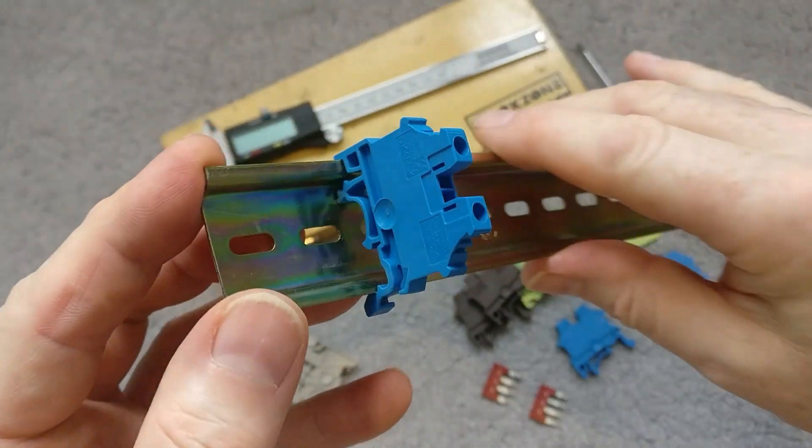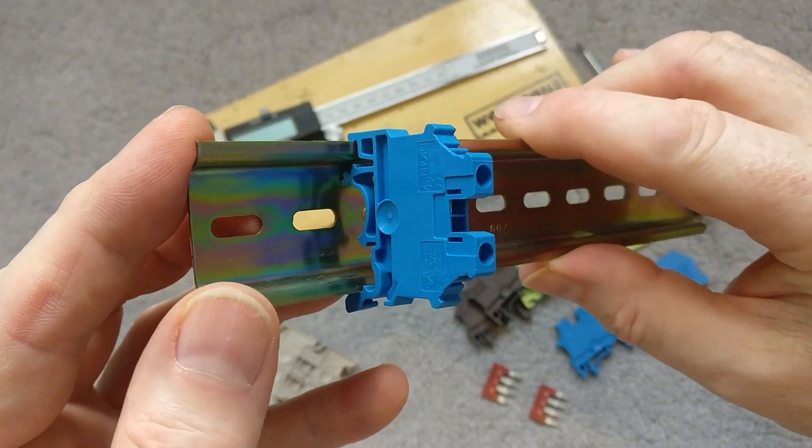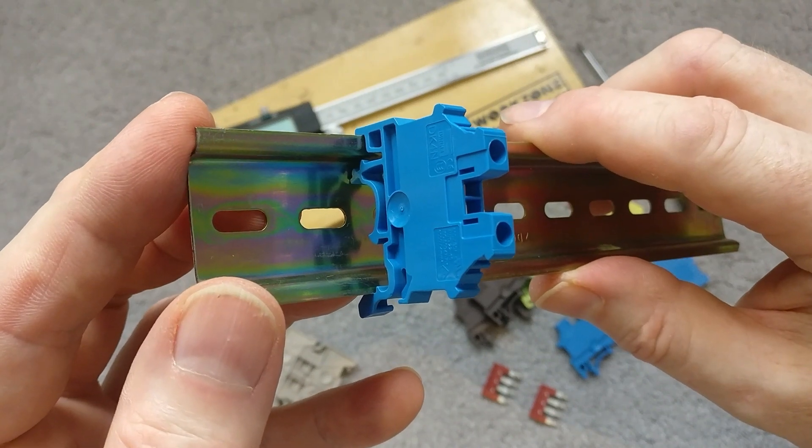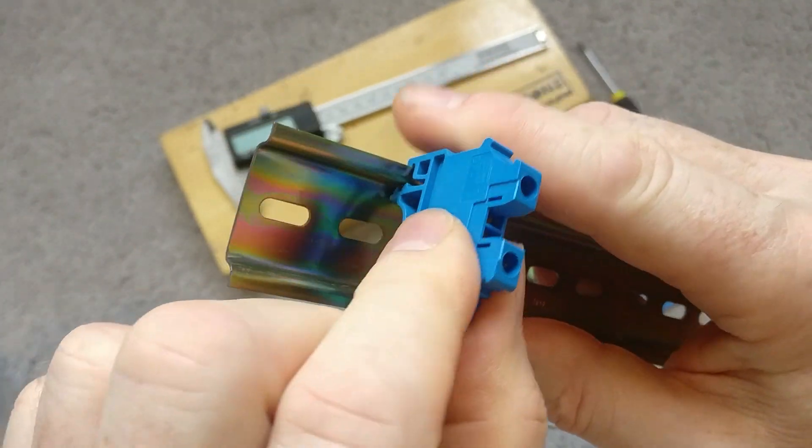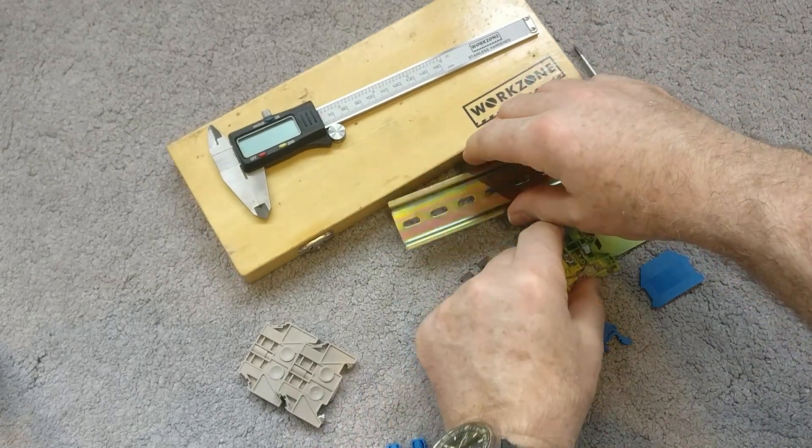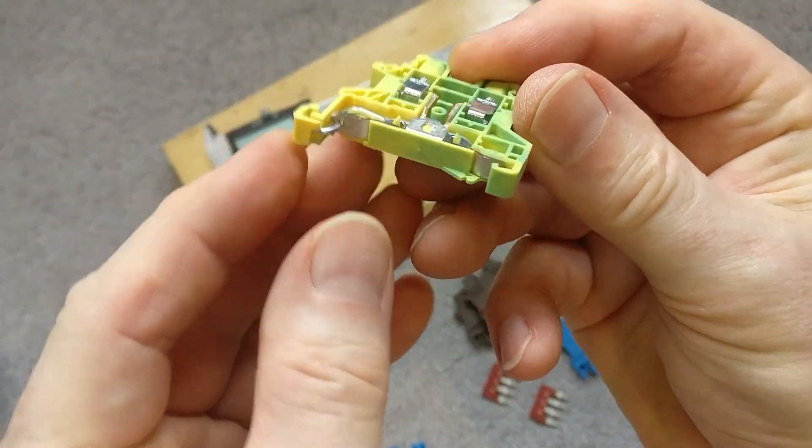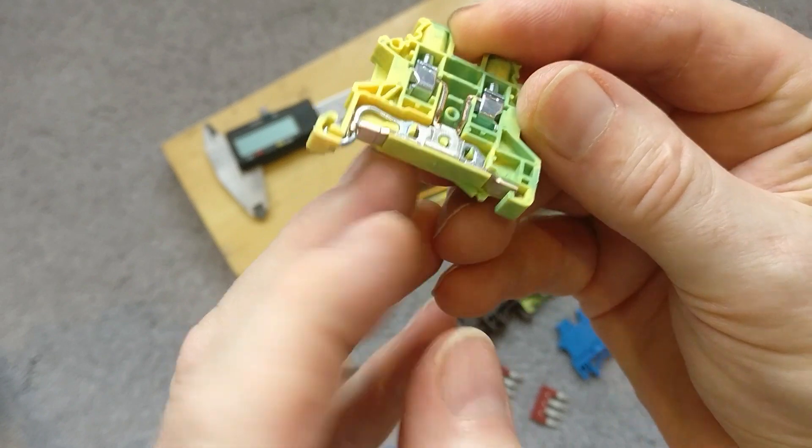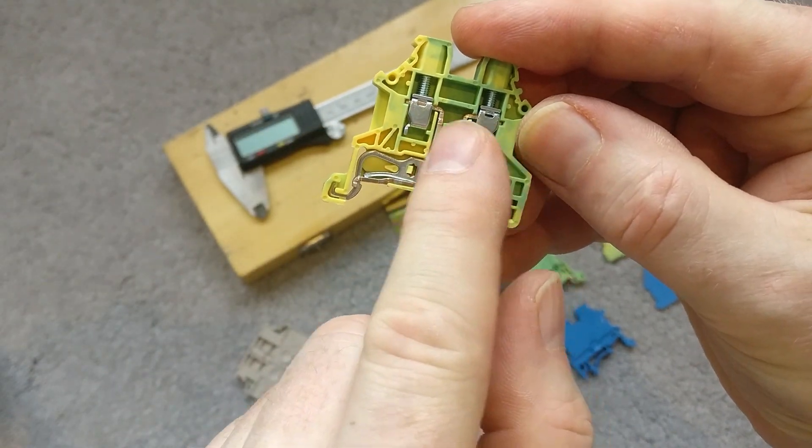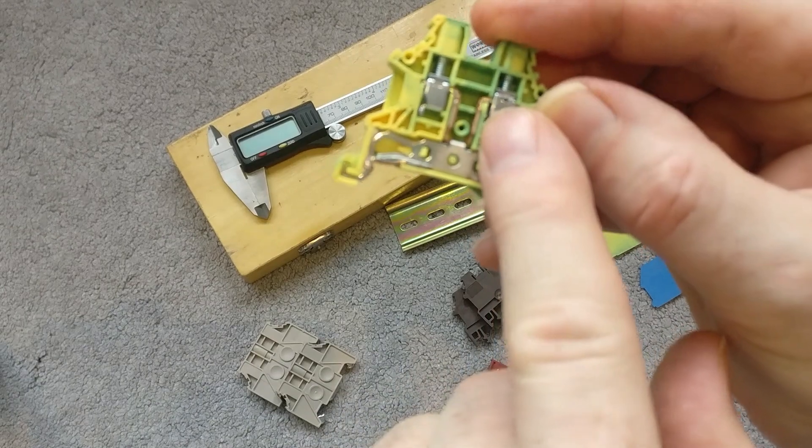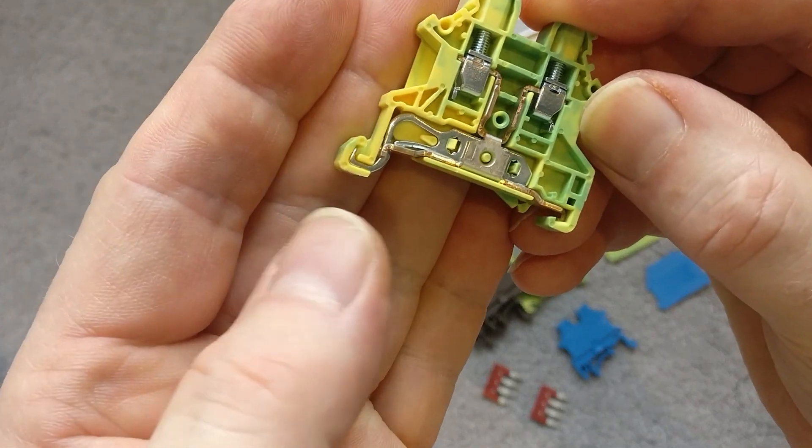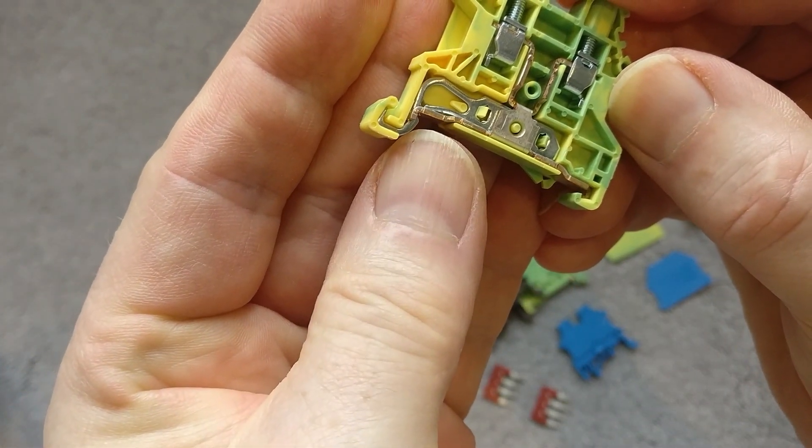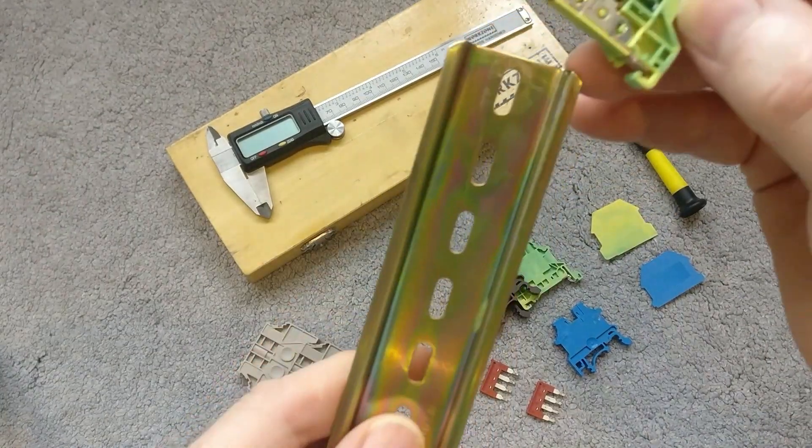They don't all work like that. The neutral terminal block and live work the same way, but the earth is slightly different. If you look at the earth connector, there's actually metal at the bottom. This means that the earth terminals here are connected through these copper rails to the bottom, and therefore they transfer the earth onto the DIN rail itself.